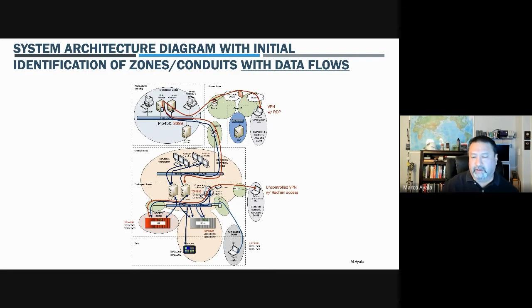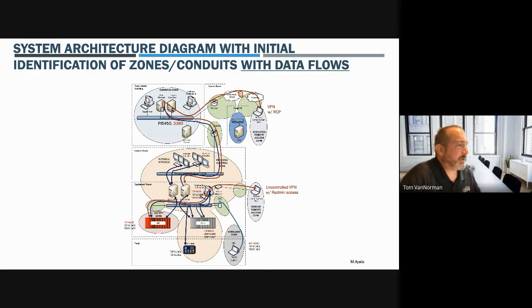When we talk about placement of sensors and placement to look at the data, a lot of people were just looking at north-south traffic. Things going from your control room zone down to your equipment room zone, for example, or control room up to your enterprise. That's what we call north and south. East and west is everything within that zone, or within that one control room, for example.